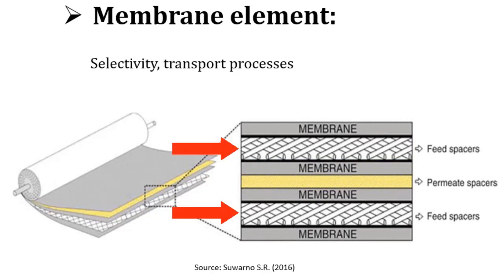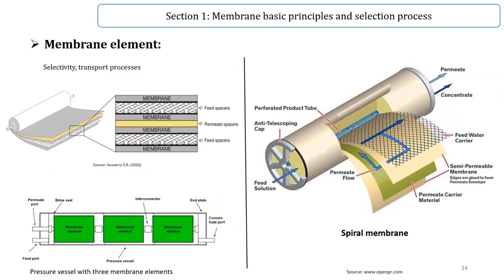Once feed is discharged to the element, it first flows to the feed channels, and then after passing through the membrane, goes to the permeate channel and is discharged to the permeate tube. There is also a pressure drop between feed and permeate sides, which will be discussed in Section 4: Membrane Design.